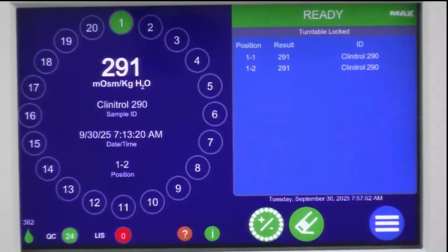So let me take you through first the main screen on the user interface here. So the first thing you're going to see on the bottom left here, and you can't really see my finger. Oh, there it is, popping up down there on the bottom left-hand side, is your test counter. So remember, I said you needed to change that Max 500 kit every 500 tests. That's really the only user intervention that needs to happen on this instrument in a 500 test cycle. And it's going to count down from 500 each time you install a new Max 500 kit.